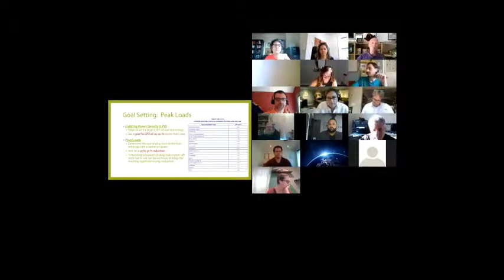I had one of my interns go out into the area we were designing the building for, turn over all the stuff plugged into the walls, and write down the nameplate information for the maximum power draw. Added it all together and it came up to 10 watts per square foot. Time and again we've gone back and said, wait a minute, not all that stuff is going to be on at the same time, and none of it will pull that maximum load simultaneously—let us figure out what you're really using in that space.